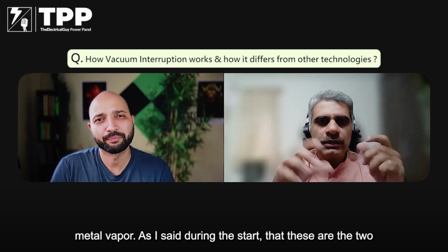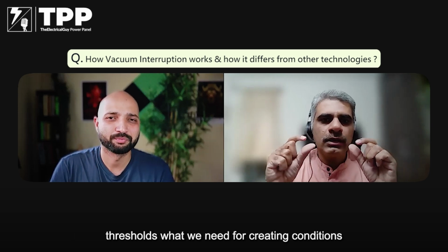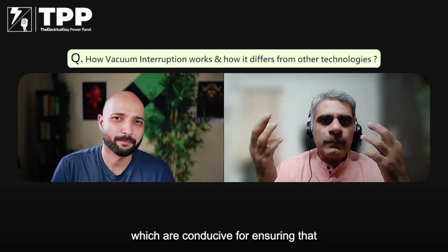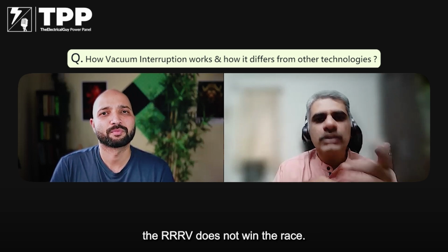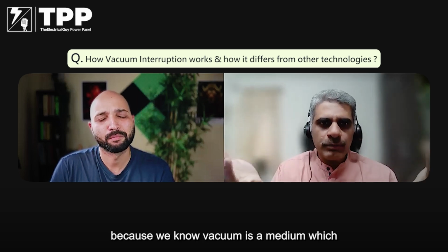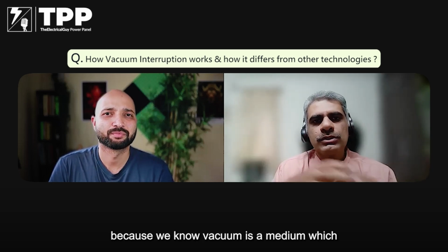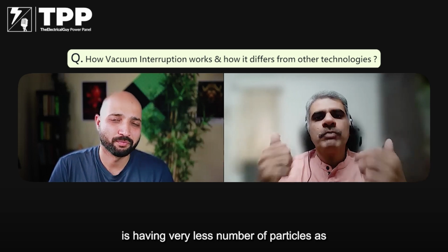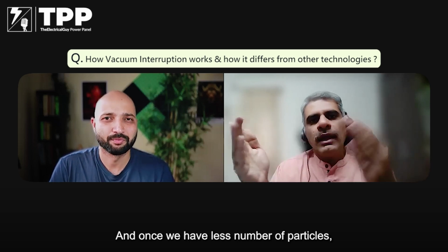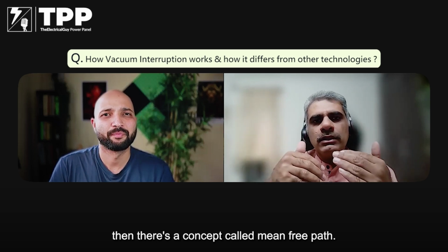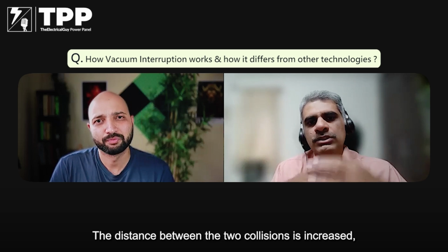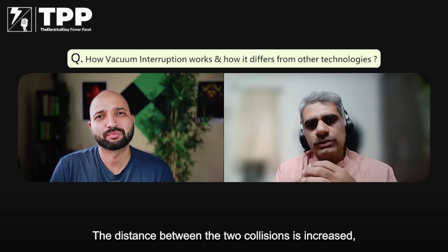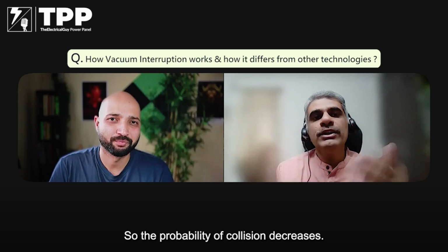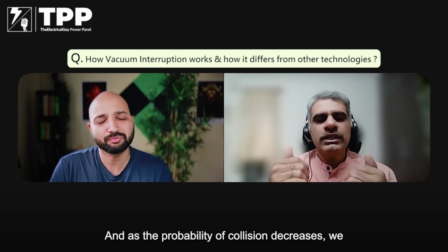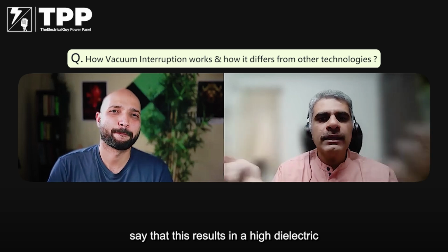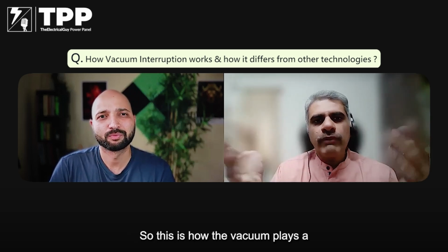As I said during the start, these are the two thresholds we need for creating conditions which are conducive for ensuring that the RRRV does not win the race. And then the rest, the vacuum takes care, because we know vacuum is a medium which has very few particles compared to normal atmospheric pressure. And once we have fewer particles, there's a concept called mean free path. The distance between two collisions is increased. The mean free path is increased, so the probability of collision decreases. And as the probability of collision decreases, we say that this results in a high dielectric strength of that medium. So this is how the vacuum plays a role.